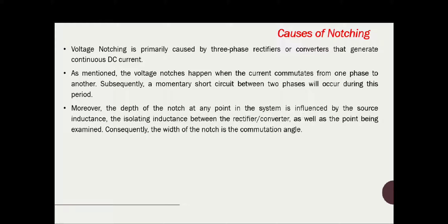Voltage notching is primarily caused by normal operating devices like three-phase rectifiers or converters that generate continuous DC current. Voltage notches happen when the current commutates from one phase to another, and subsequently a momentary short circuit between two phases will occur during this period. Moreover, the depth of notches at any point in the system is influenced by the source inductance and the isolating inductance between the rectifier or converter and the point being examined.